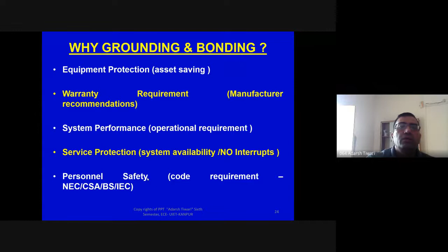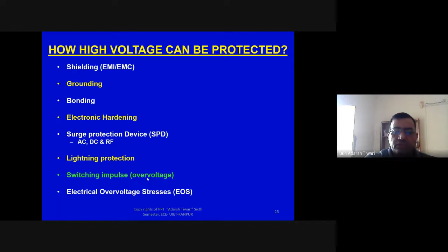Now, how can this high voltage be protected? First of all, shielding is a very common method. Then we have to do grounding, bonding, and electronic hardening, which is very specialized electronics, used mainly for space applications where the radiation is more. In the case of sophisticated electronics, surge protection devices are very important, and they come in the flavor of AC surge protection, DC or RF. Lightning protection is also very important for high-rise buildings, and electrical overstress and electrical switching impulses are very common in power systems.